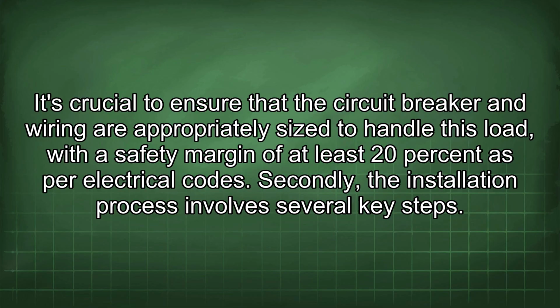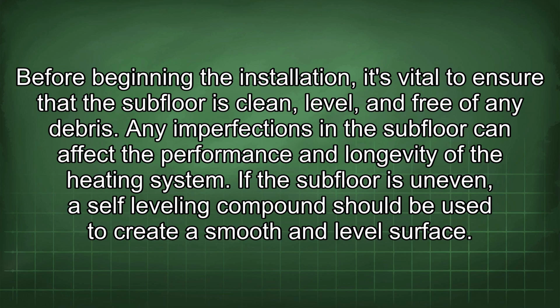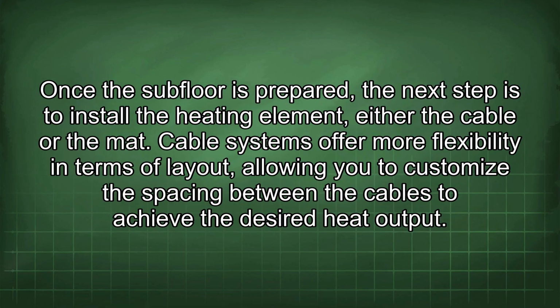Secondly, the installation process involves several key steps. Before beginning the installation, it's vital to ensure that the subfloor is clean, level, and free of any debris. Any imperfections in the subfloor can affect the performance and longevity of the heating system. If the subfloor is uneven, a self-leveling compound should be used to create a smooth and level surface. Once the subfloor is prepared, the next step is to install the heating element, either the cable or the mat.